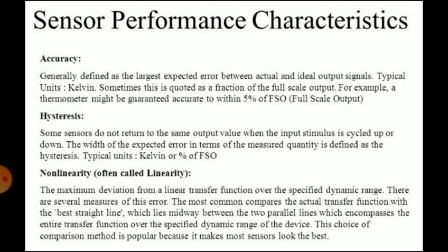Then non-linearity, often called linearity. It is the maximum deviation from the linear transfer function over the specified dynamic range. There are several measures of this error. The most common compares the actual transfer function with the best straight line, which lies midway between the two parallel lines which encompass the entire transfer function over the specified dynamic range of the device.